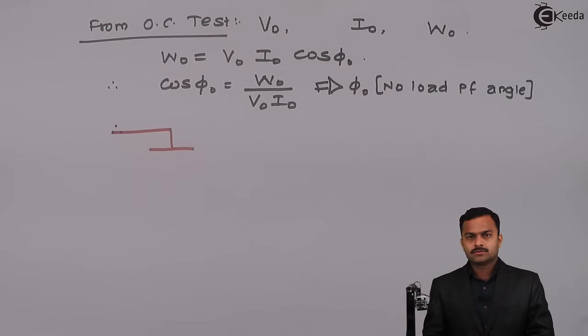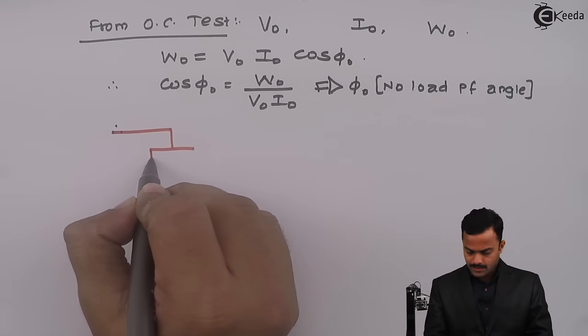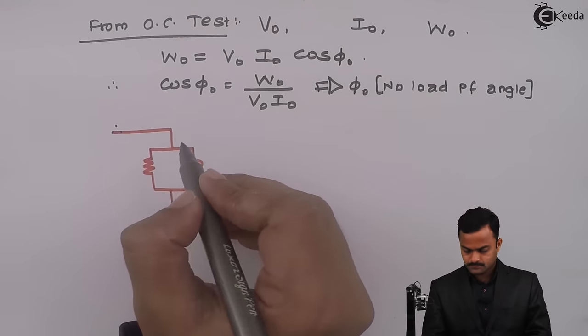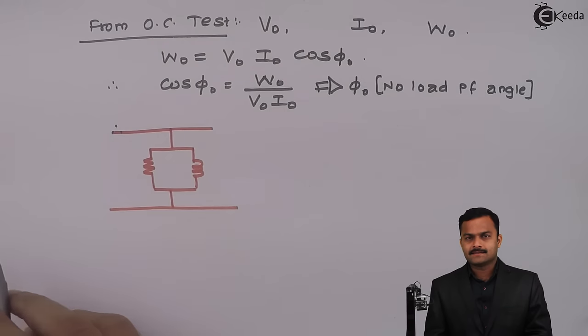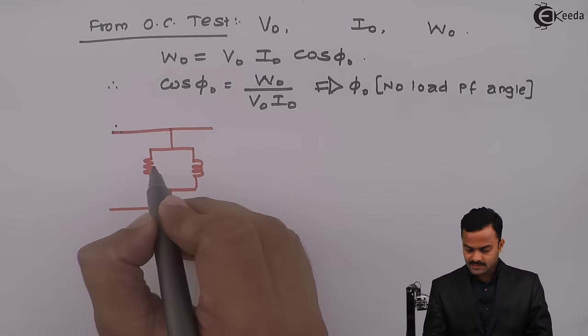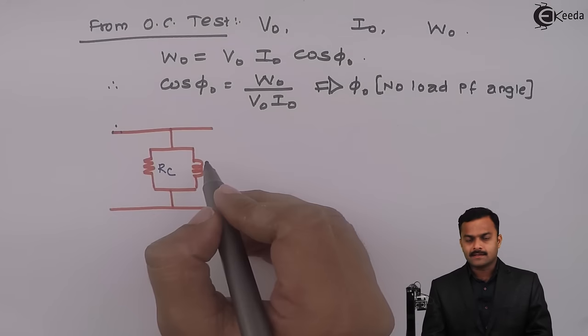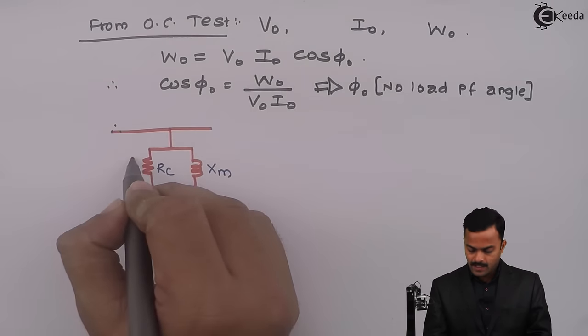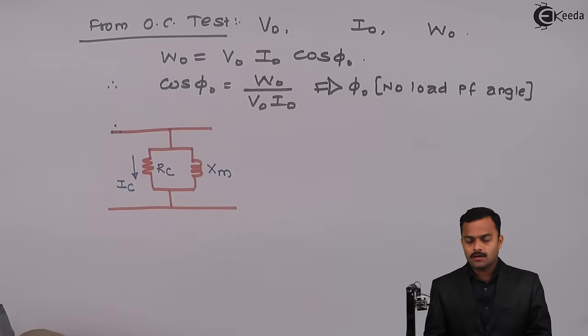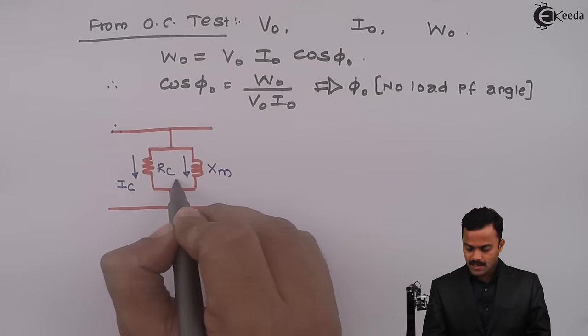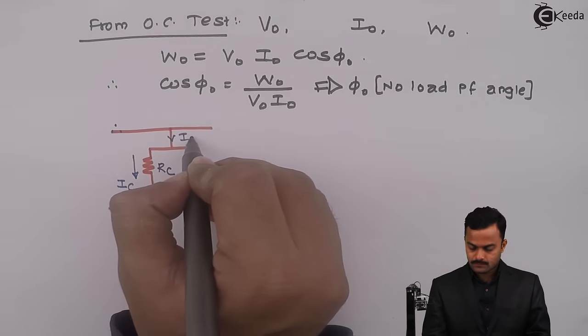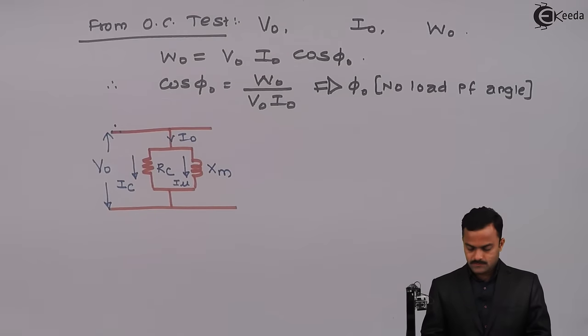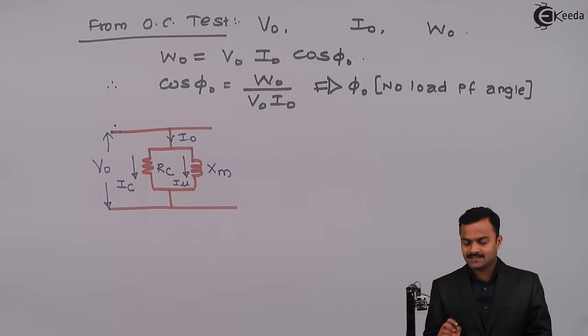The equivalent circuit at no load has a parallel combination of one resistance and one inductance. The resistance is called core loss resistance RC, and the inductance's reactance is the magnetizing reactance XM. The current carried by RC is the core loss component of I0, denoted IC, and the current carried by XM is Iμ, the magnetizing component of I0. The no-load voltage across them is V0. The objective of the OC test is to get the values of RC and XM.